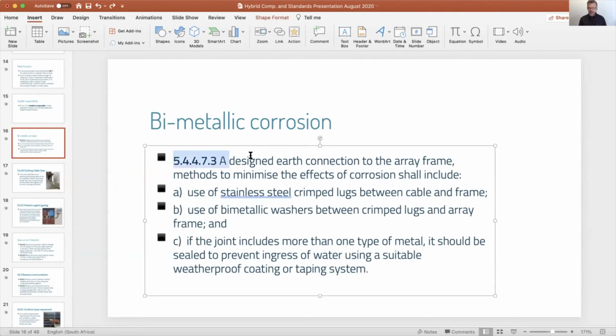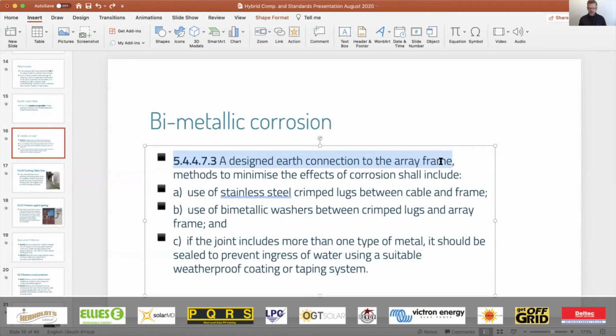5.4473 says a designed earth connection to the array frame. Methods to minimize the effects of corrosion shall include the use of stainless steel crimped lugs between the cable and the frame, or the use of bimetallic washers between crimped lugs and the array frame. And then it goes further to say that if the joint includes more than one type of metal, it should be sealed to prevent ingress of water using a suitable waterproof coating or taping system.